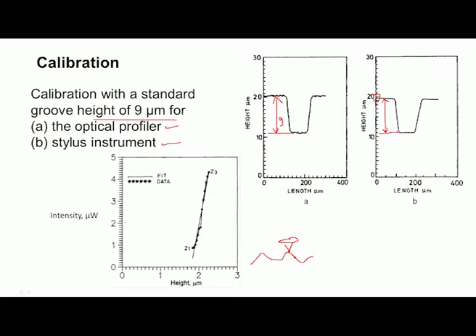And then the reflected light intensity is measured in terms of microwatt. You can see the reflected light intensity varies from 1 microwatt, 2 microwatt like this, with the corresponding height of the point. Depending upon the light intensity, as the light intensity varies, the height of the point also varies. Okay. So, like this we have to initially calibrate the system, and then we can use it for assessment of the surface.